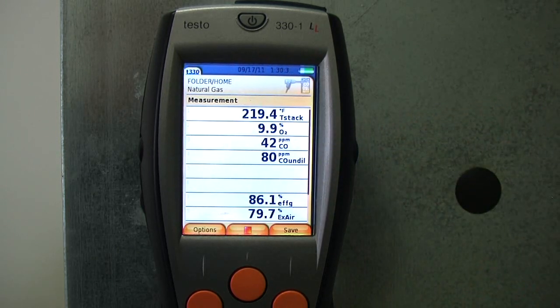So here we're going to kind of keep an eye on it. Now if that number were to go up any at all now that the blower just kicked on, we would know that there's a sign that there's a leakage. It could be a bad seal, could be a crack in the heat exchanger, could be whatever. But that's what we're looking for. We're looking to see if this number raises.